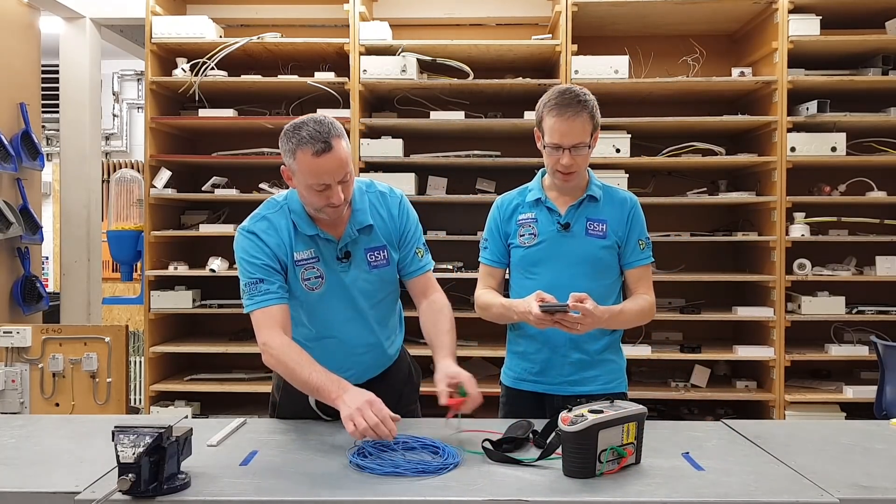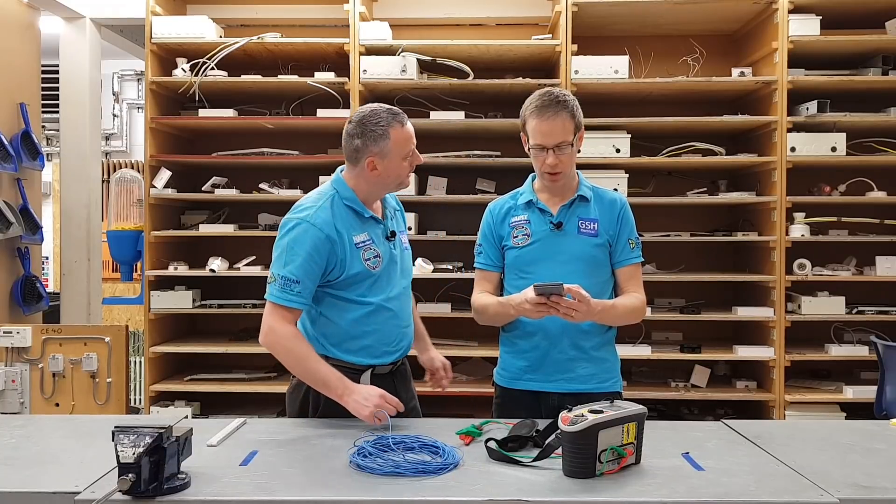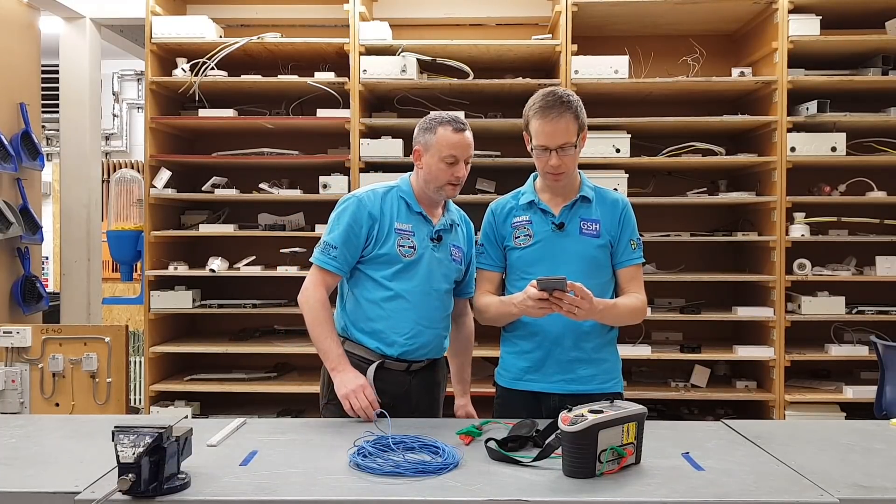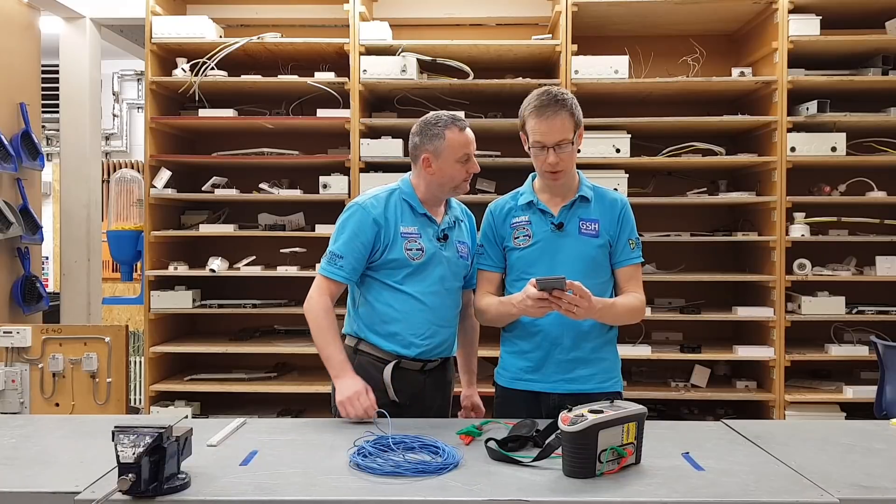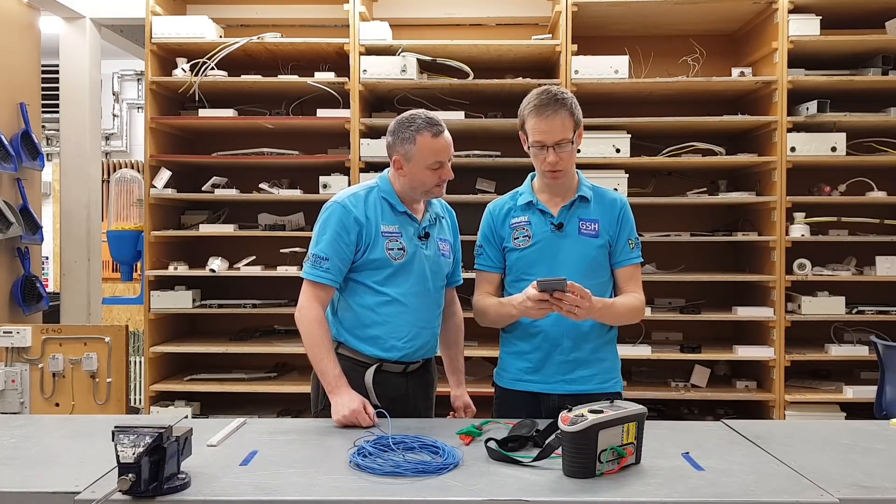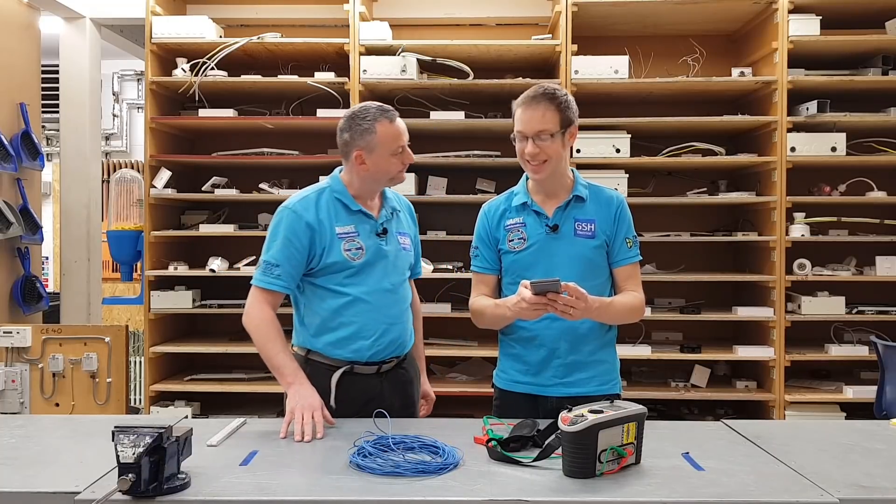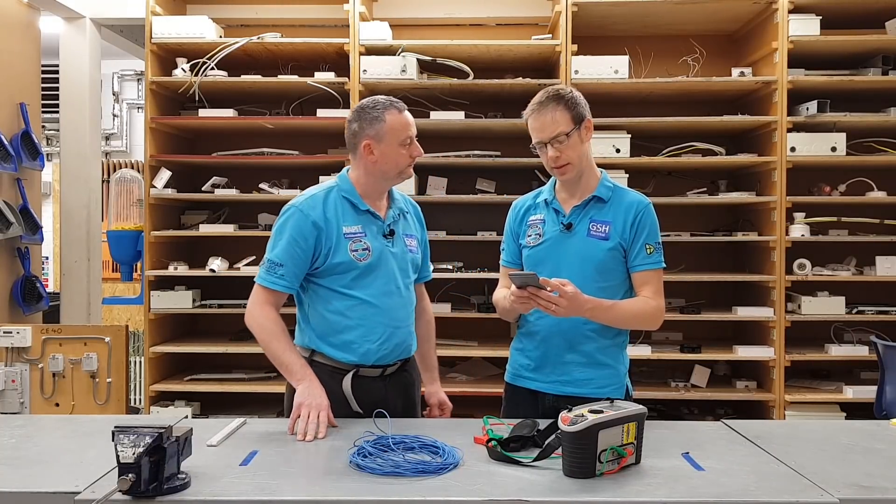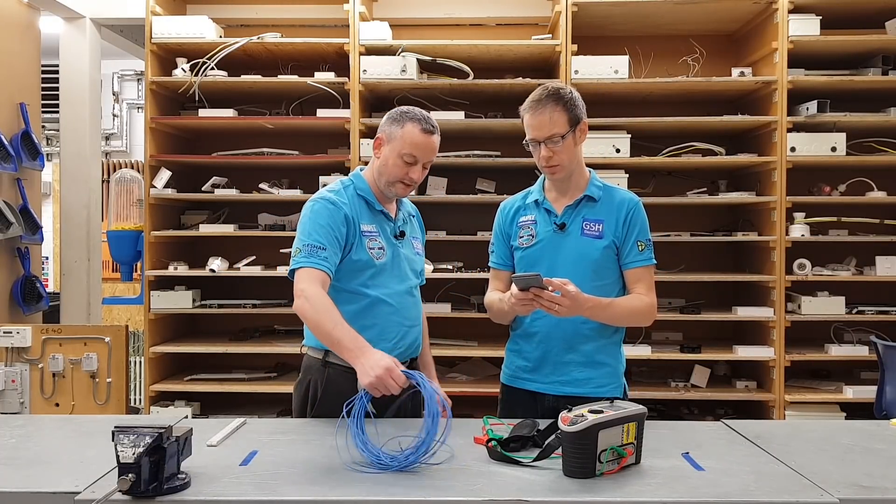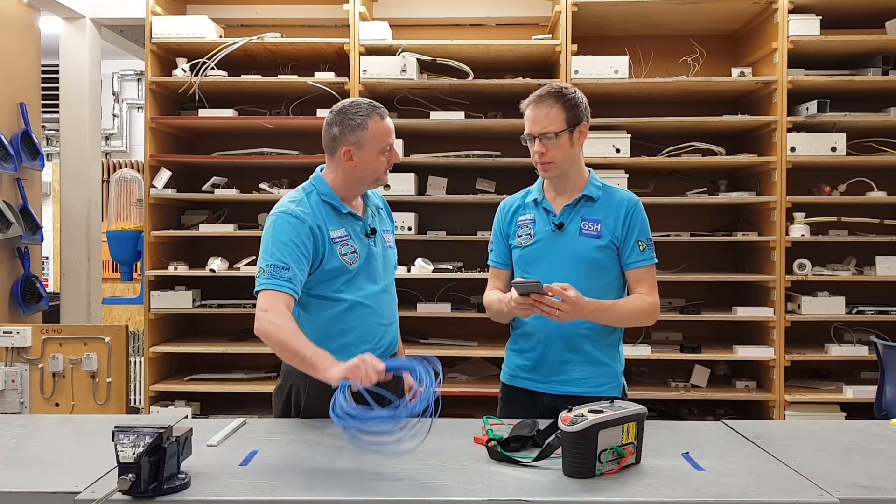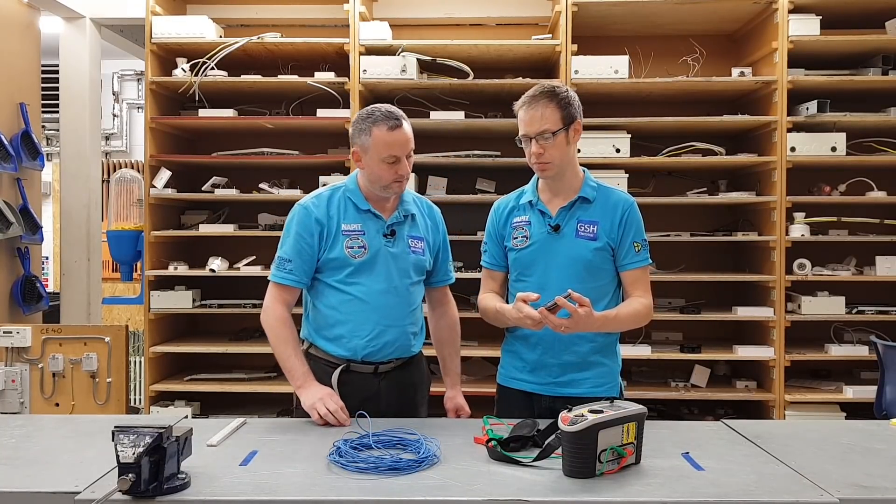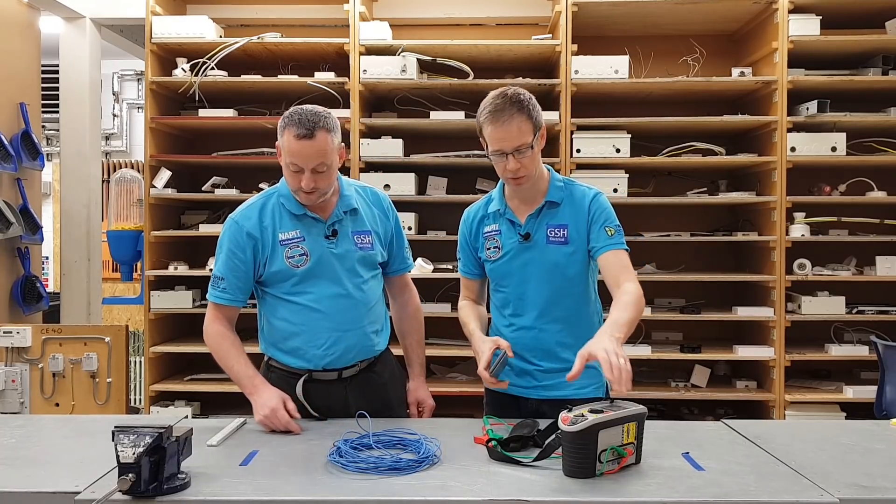Okay, right, I think we can do this then. So if I take that resistance of 0.19 and then I times it by the cross-sectional area, that's a lot of numbers. We're coming out with we should get about 16 and a half meters of cable. So you think 16 and a half meters here with your clever maths? Approximately yeah, 16 and a half, somewhere in that area.